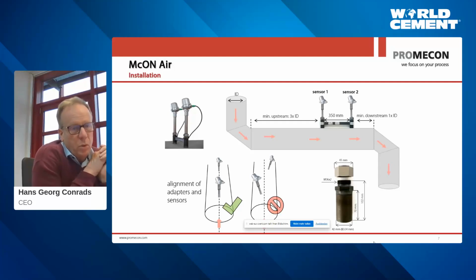The downstream distance for us is not important because we are not measuring any pressure changes. For us, pressure change is not an issue, right? The only pressure we need is the barometric pressure. Whether the pressure is a few millibars up or down will not change the density of the air significantly. So barometric pressure is enough. And then, of course, for density, the big thing is temperature. If you have a duct with a venturi-like zone, so you have a duct that has a tapered section inside, then, of course, that section is the best possible place for us to measure. If you don't have that, such as on a downcomer, you just mount our sensors on the downcomer directly, and then you make sure you have enough upstream IDs so that we can then have a straight flow around the sensors, and we can measure your velocity.